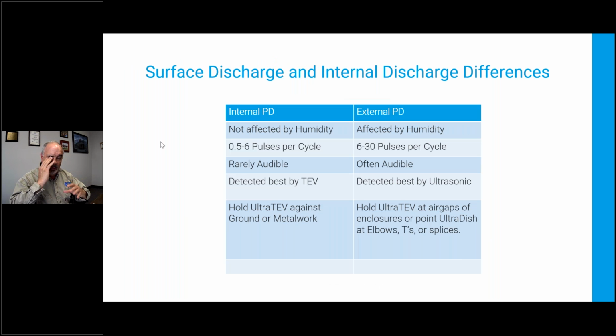So just a quick summary on surface and internal discharge before we move on. Internal discharge is not going to be affected by humidity, whereas surface discharge would. The pulse counts are different. You're never going to hear internal PD, and TEV is your best measurement technique. For external PD, it's ultrasonic. We don't know what we're looking for, so we're going to do both tests.